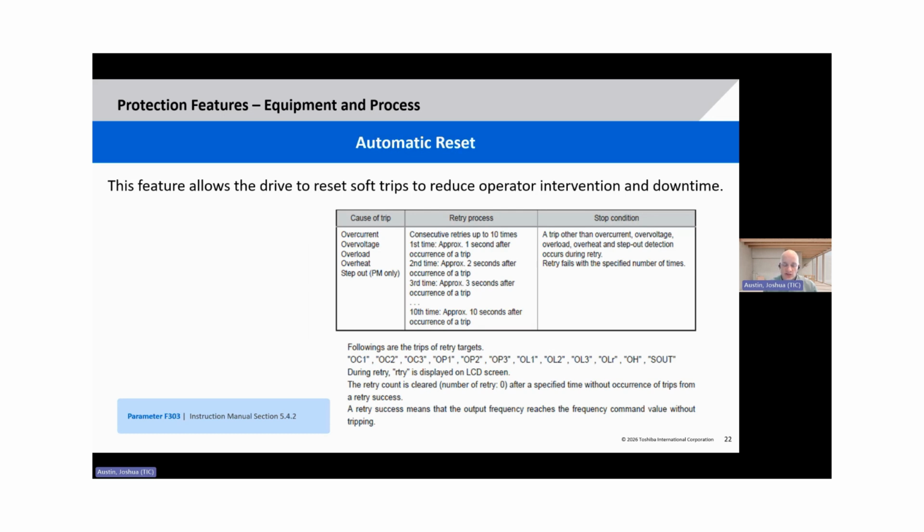Looking at reducing downtime, we have the automatic reset function. What this feature allows you to do is automatically reset certain faults that we have defined as soft faults or non-critical faults. And so you can see a list of these here. We have overcurrent, overvoltage, overload, overheat.